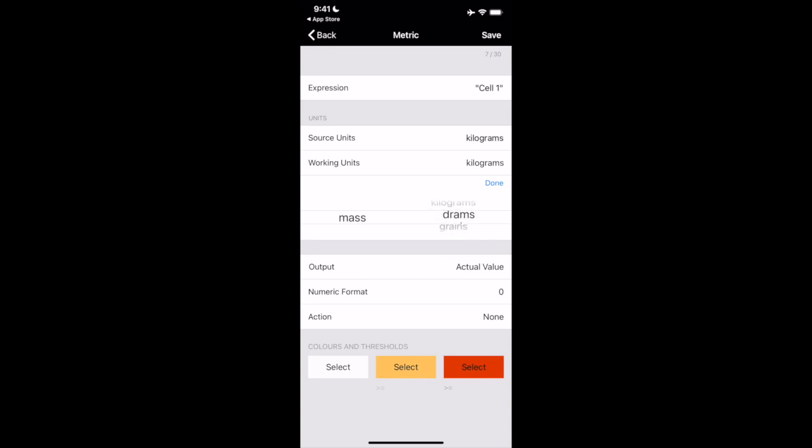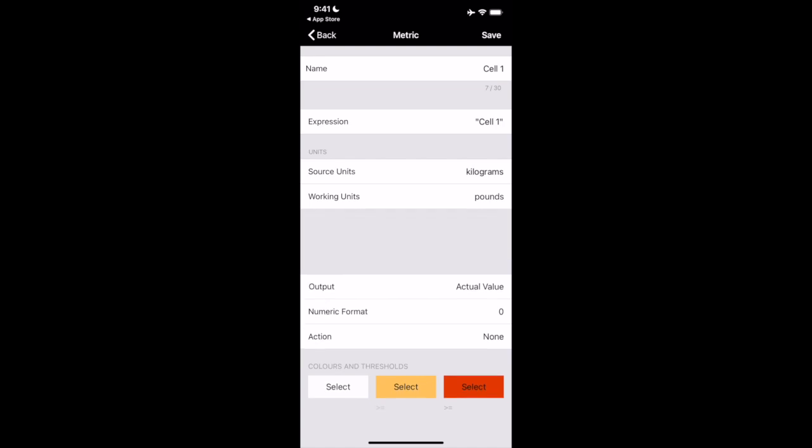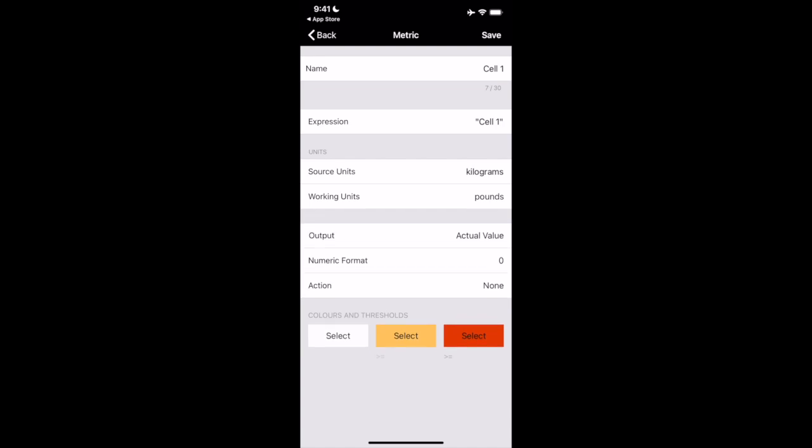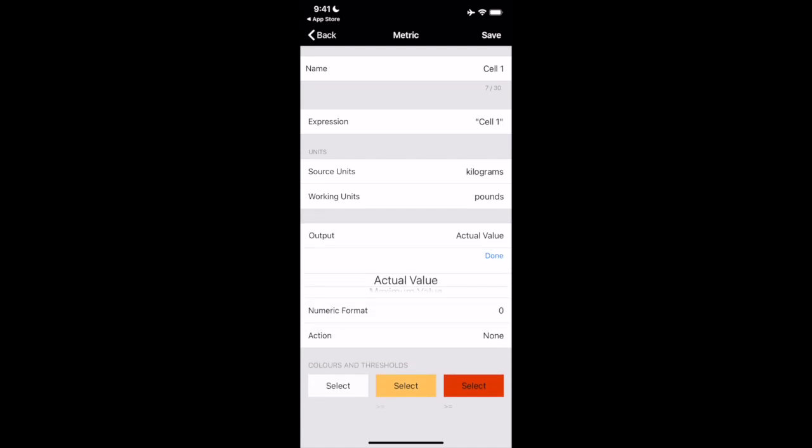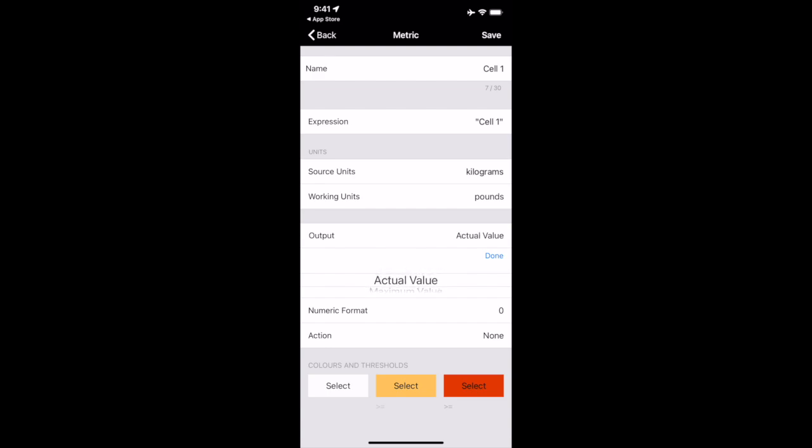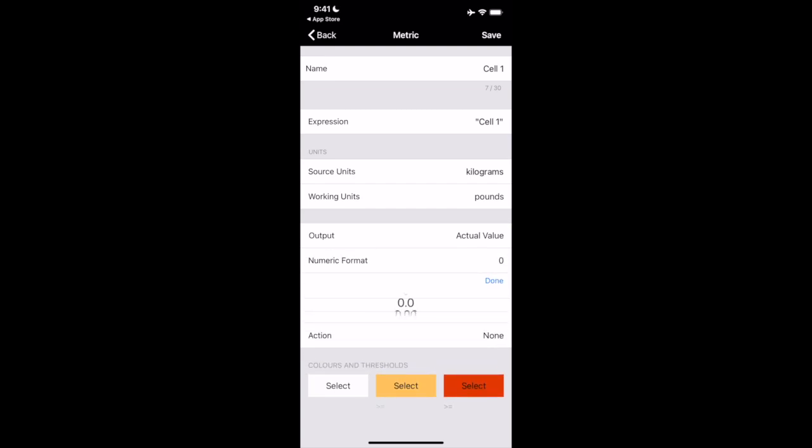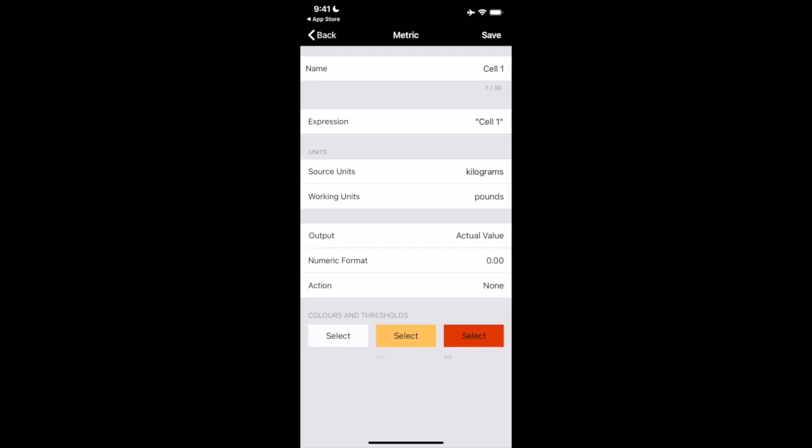Working units is the units that we're going to be working in. We are going to call that, we have wide variety options in here. Most likely in North America, we're going to be going to pounds. But as mentioned, if you want anything else in here, full options. So we're going to take ourselves to pounds. Output value. I have option to do actual value, maximum value. So kind of peak hold of an item or minimum value. So it's kind of a trough hold out of that. Maximum value. Sometimes neat to see the max kind of weight captured on that load cell and whether you did a separate tile for that to see, but we're going to do actual value. Numeric format is kind of how many decimal places we're seeing. So for this purpose, let's do 0.00 in here. So we have a few more decimal places.